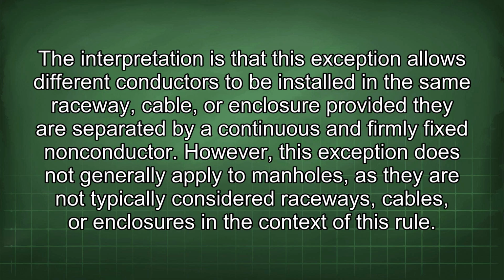The interpretation is that this exception allows different conductors to be installed in the same raceway, cable, or enclosure provided they are separated by a continuous and firmly fixed non-conductor. However, this exception does not generally apply to manholes, as they are not typically considered raceways, cables, or enclosures in the context of this rule.